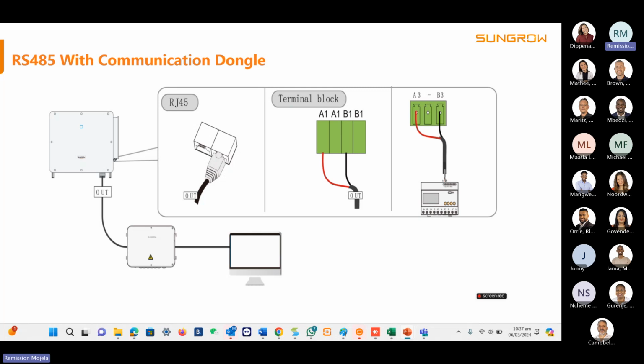So the meter always sits on a different COM port to the Sungrow devices, since it's a third-party meter. Normally we use the Acrel DTSD1352. So that sits on a different COM port than our inverters, because if you put it on the same COM port as the inverters, we won't be able to pick up the meter, because the meter we normally don't actually pick up. We just add it separately as a separate device. But the inverters themselves, the moment you connect them on the bus, you'll automatically pick them up.